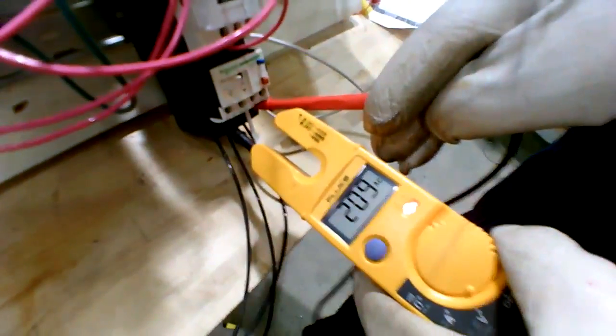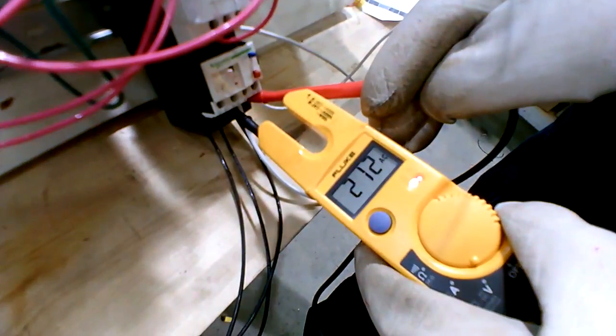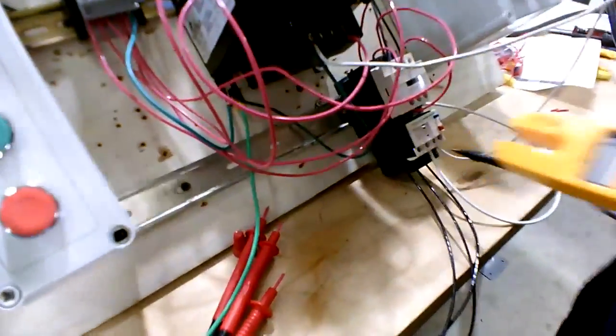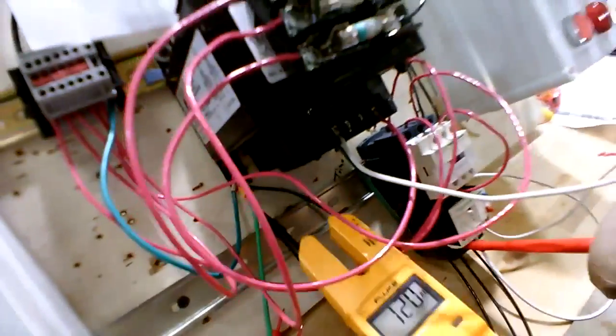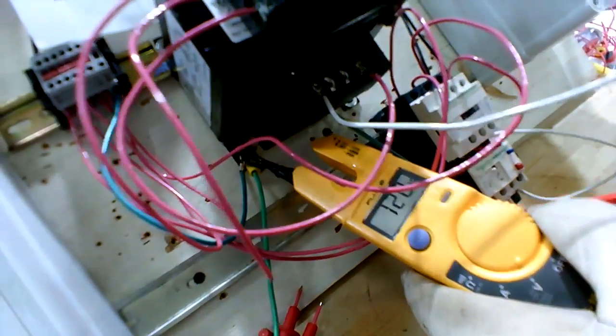In this position where we can see good, you hold the meter back there. You got 211 when you go from phase 1 to 2, 210 for 1 to 3, 209, and then 2 to 3 is 212. It's in the range of 208. And it goes from each one of those to ground. Use the ground up here. Move the plug. It should be 120. It is, and then check all 3 legs. Yep.